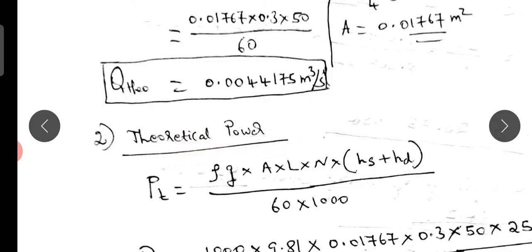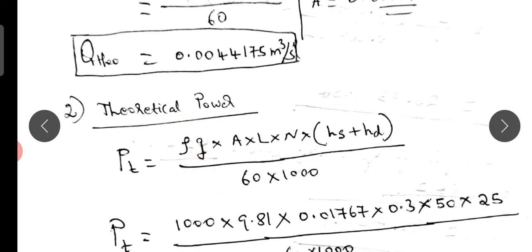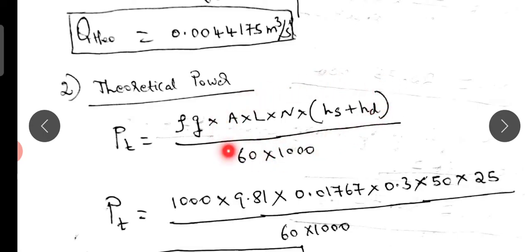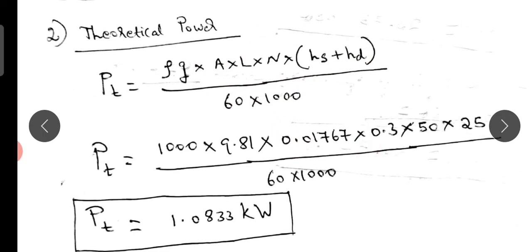Theoretical power: substituting the given values into the power formula using total head of 25 metres and theoretical discharge, the theoretical power required to run the pump is 1.0833 kW.